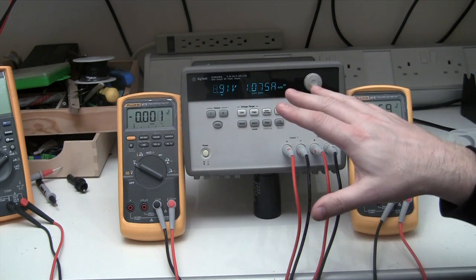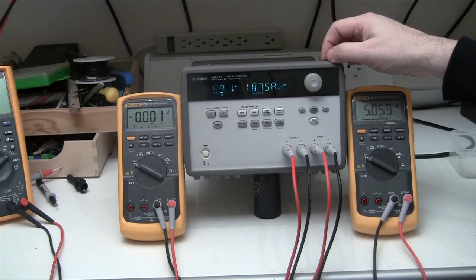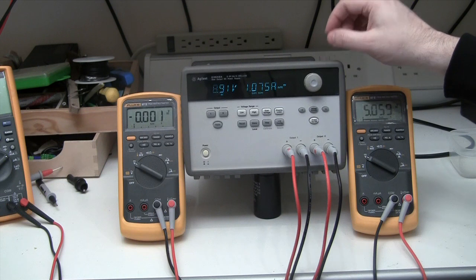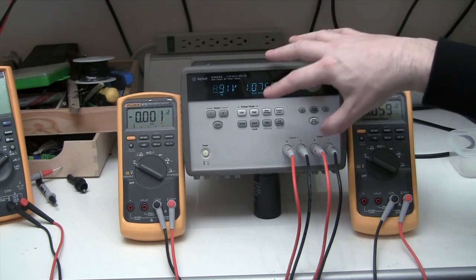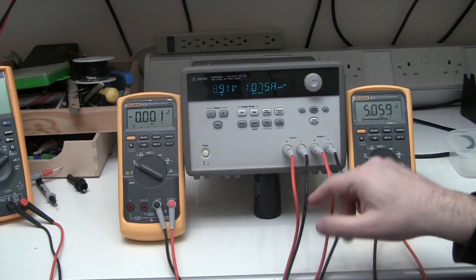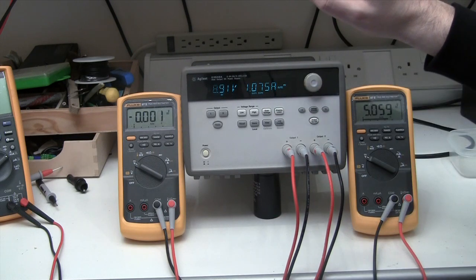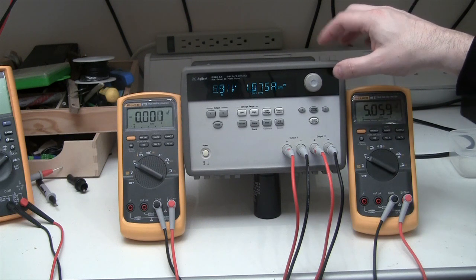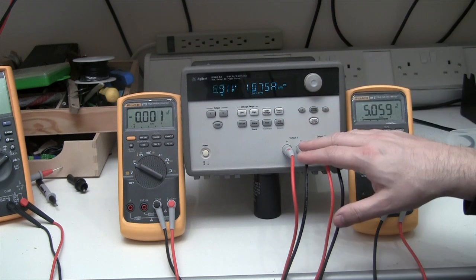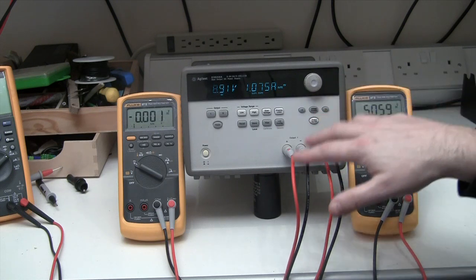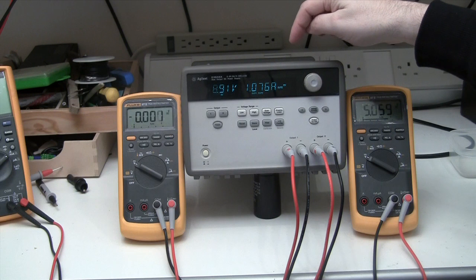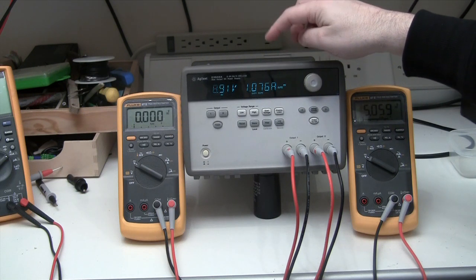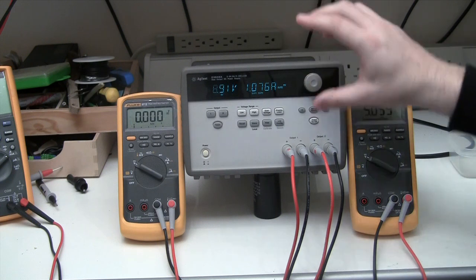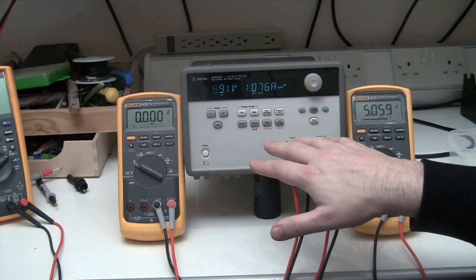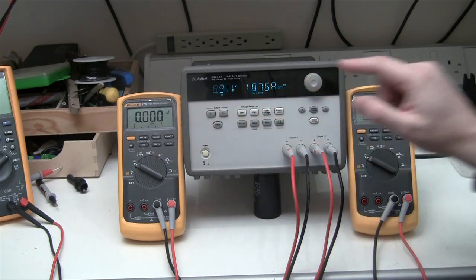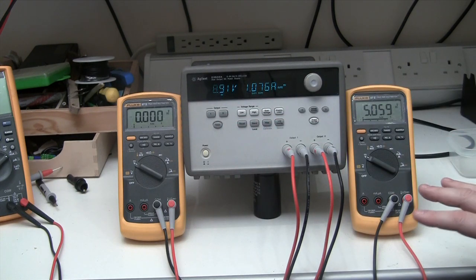What's curious about that fault is inside this power supply, the analog to digital converter circuit is used for both channels, so the 2 channels are isolated. In this one, a lot like the 3631A, there are analog opto-isolators isolating the sense and control voltages between the 2 power supplies and the main control board, which all goes to one chip, a 4051. So it's curious that although both channels are working perfectly, the readback is only failing on one channel and not both.